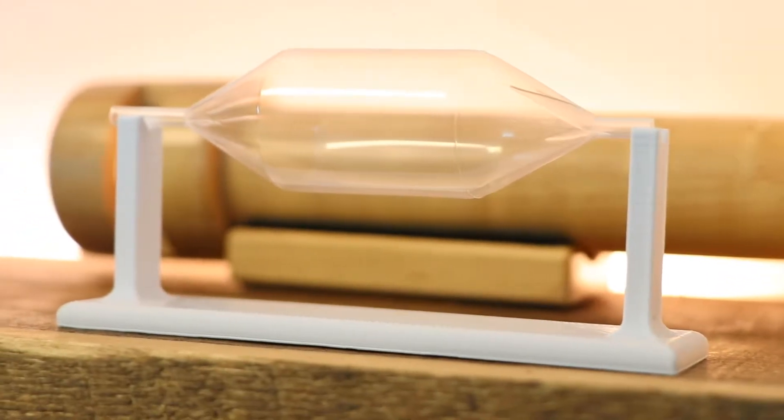One of the observations that we've had is that you can't get very large blow-up ratios with nylon 6, which means the relationship between the maximum balloon diameter and the tails of the balloon is very small. So you end up with very large profiles, and the rigidity of the material in combination with the blow-up really doesn't make it an ideal material for blow-forming medical device balloons.